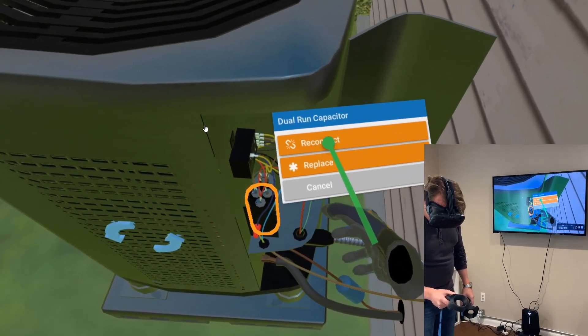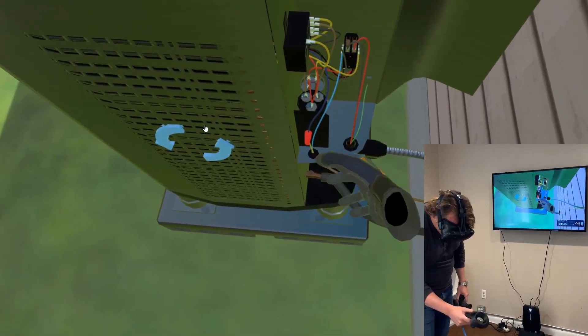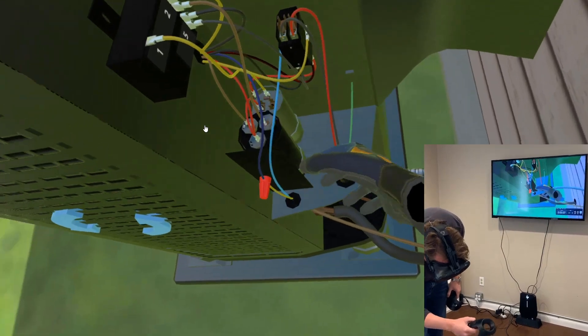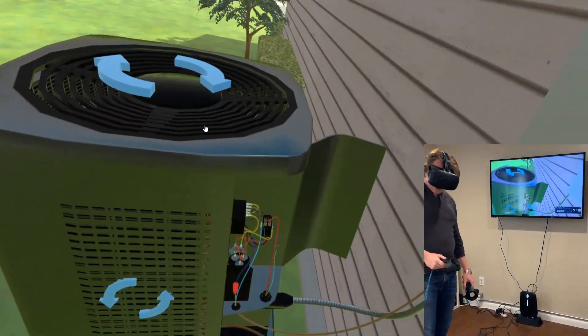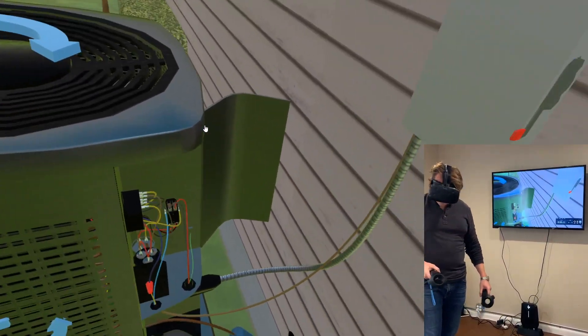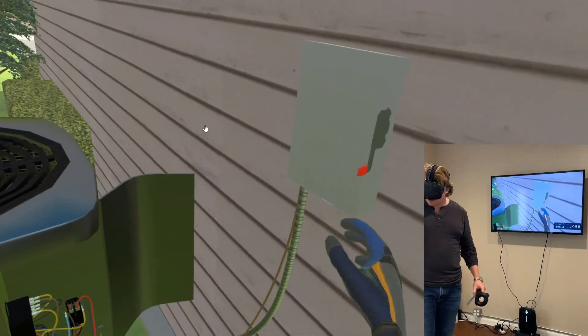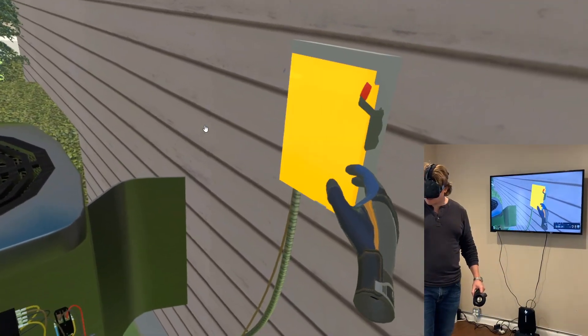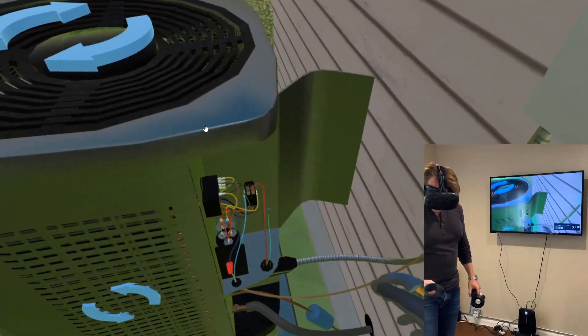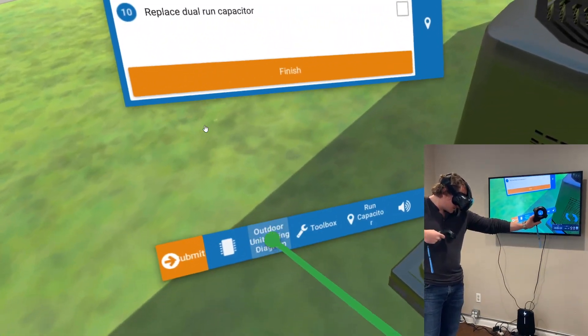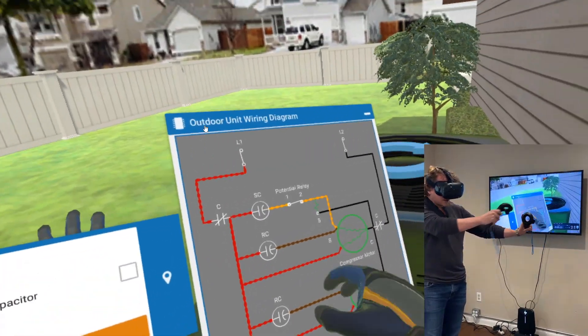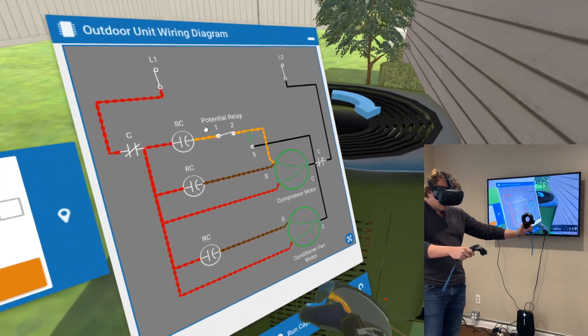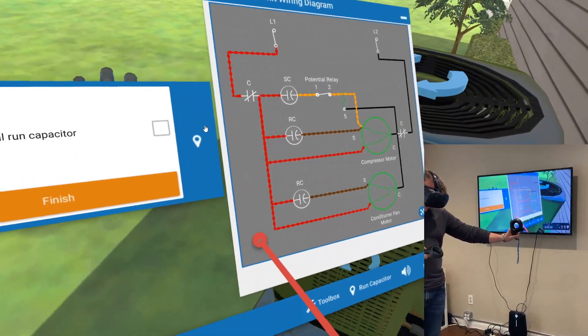That ended up reconnecting all of our additional start capacitor as well. Now I'm going to get the system tested and turn it on. I should be able to pop into our outdoor wiring diagram. I can now actually see how electricity is flowing through because with the right capacitor, the circuit is completed.